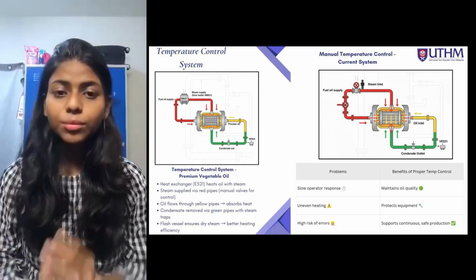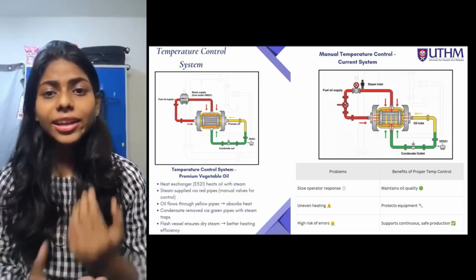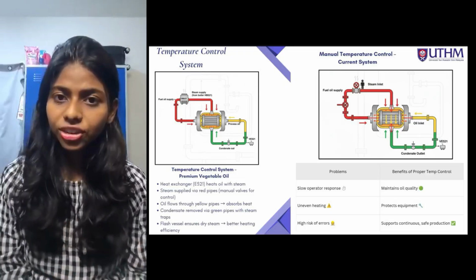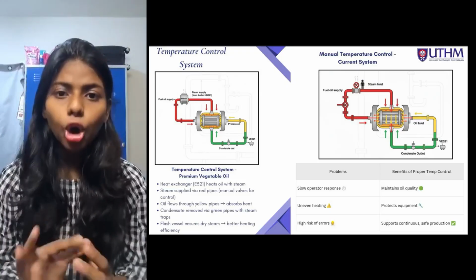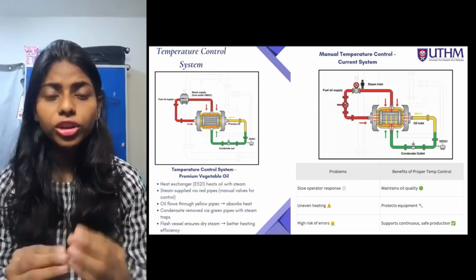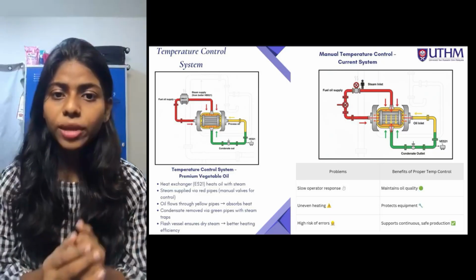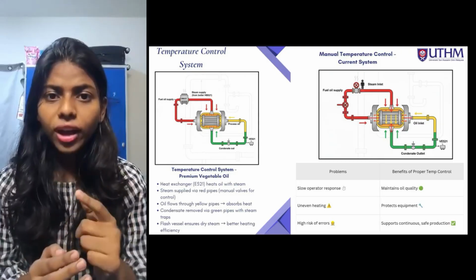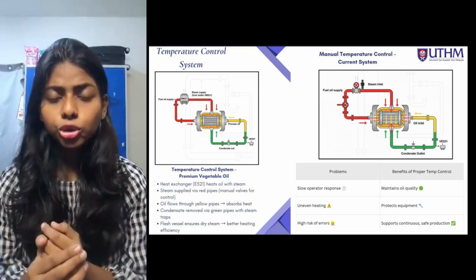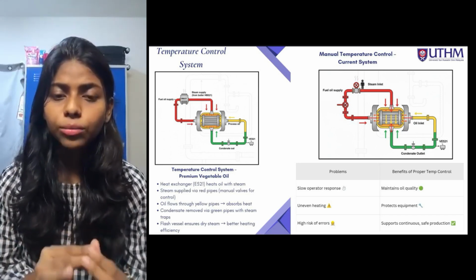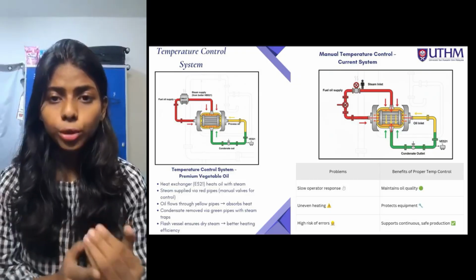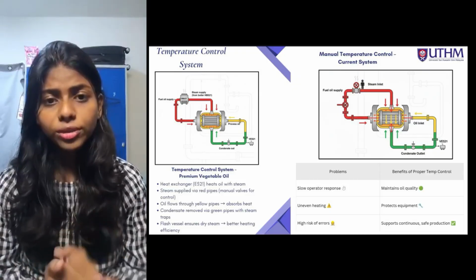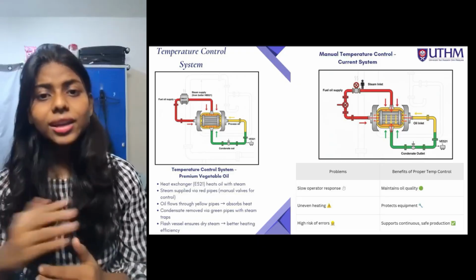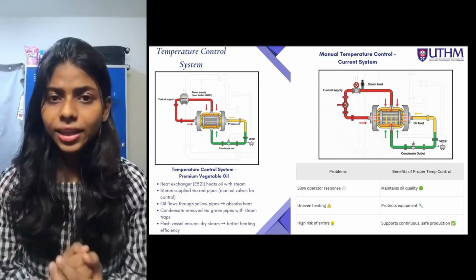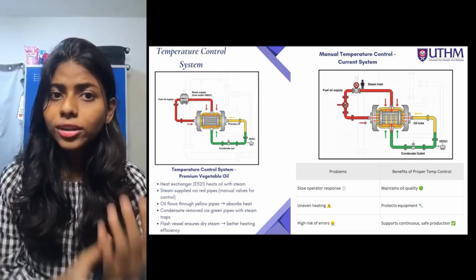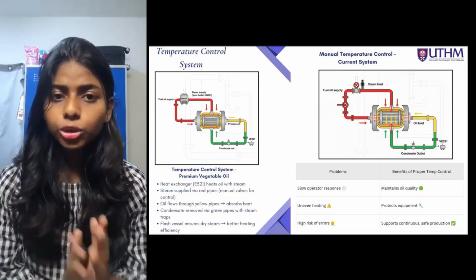This is the temperature control system of the premium oil company. The heat exchanger E521 works in the bleaching section. It uses a network of pipes to control steam flow, oil flow and condensate removal, which are important for the proper heating. The red pipes carry the steam from the high pressure steam boiler HB521 to the heat exchanger. These lines use the manual valve, so the operators must control the steam flow by their hand. The yellow pipes represent the process oil. The oil enters the heat exchanger, absorbs the heat from the steam and then flows to the next bleaching stage. After releasing heat, the steam turns into condensate. The condensate is removed by the green pipes, which are fitted to the steam traps.